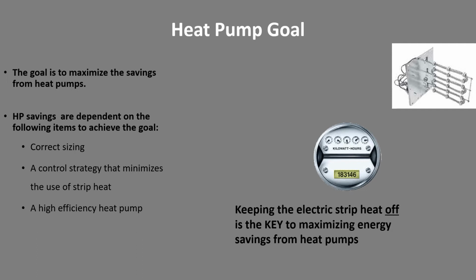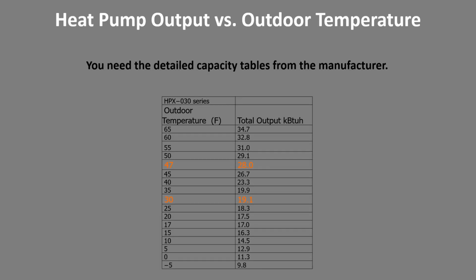Say a 3-ton heat pump draws about 3 kW and there's 15 kW worth of backup. Boy, as soon as that 15 kW backup comes on, you go from 3 kW all the way up to 18 kW. You basically increase the energy used by a factor of 6 when that happens.